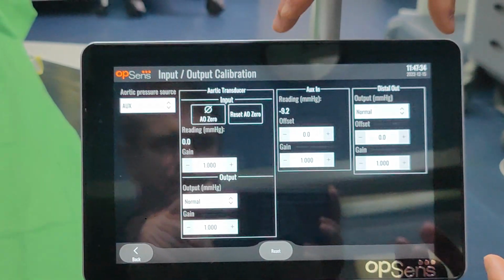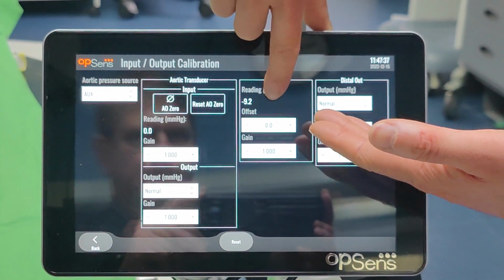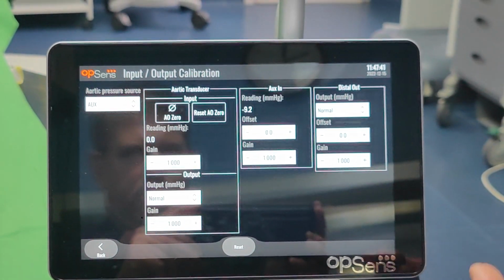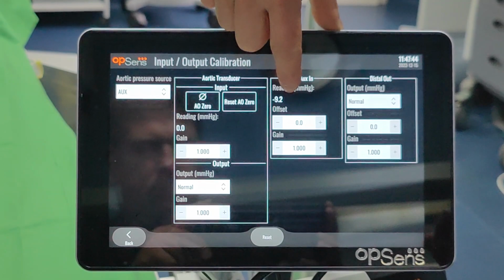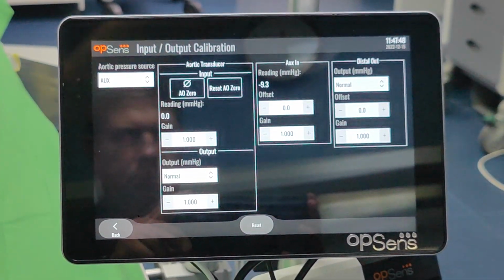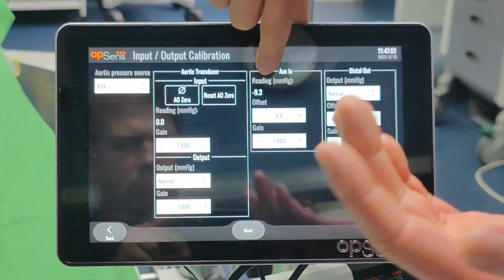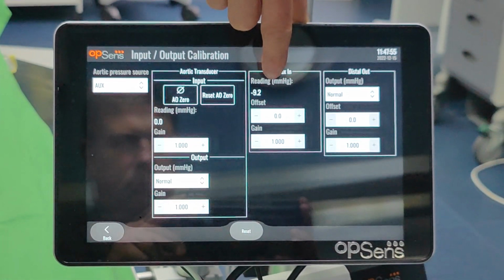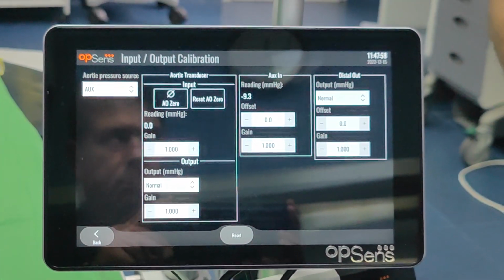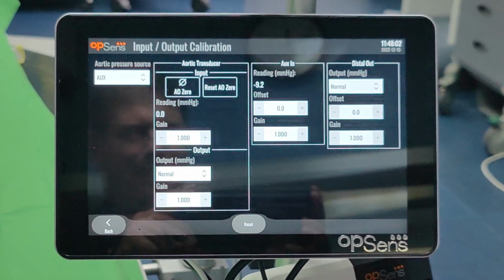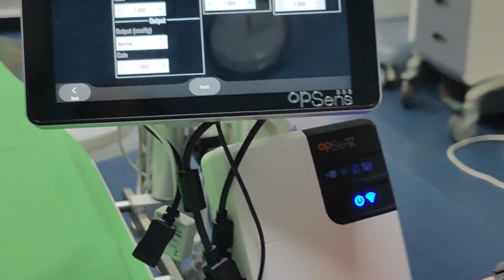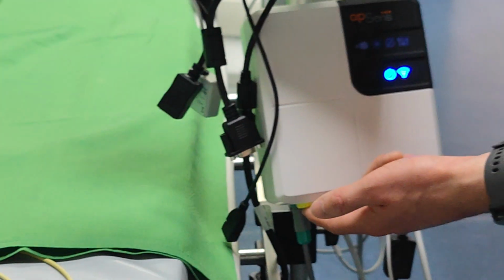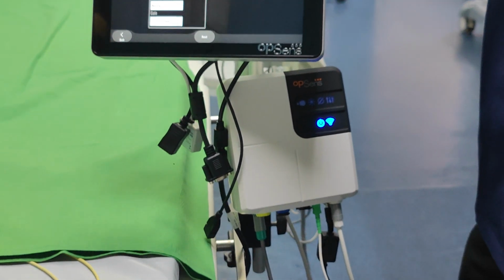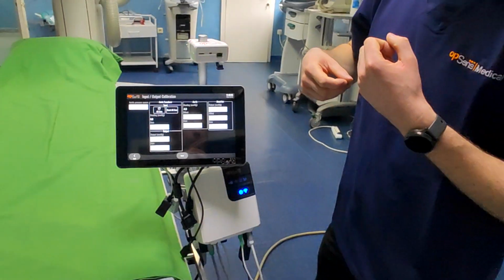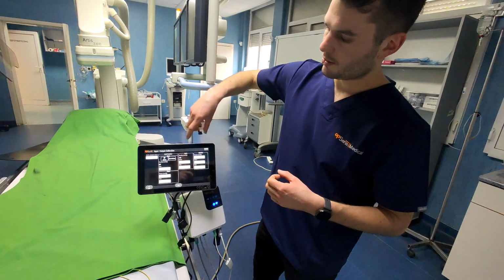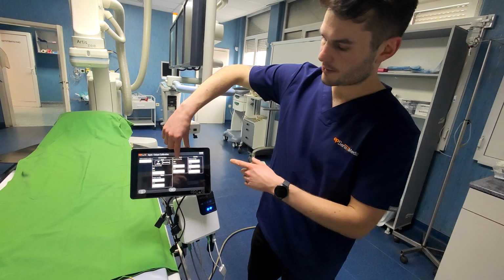But the idea is that you want to set your 0 point and also the top point. So you want your 0 to be accurate. So this is basically the system feeding in from the aortic. The aortic reading that comes from the system, you want that to be 0 on both, the same 0. So when you've got your yellow cable into the distal out, what you can do is, with the output here, set this to 0, which sends a signal to their system because you're plugged into their P1 rather than the signal from the transducer. It sends a signal to their hemo system saying 0. So if they're 0 and that's 0, this should also read 0.